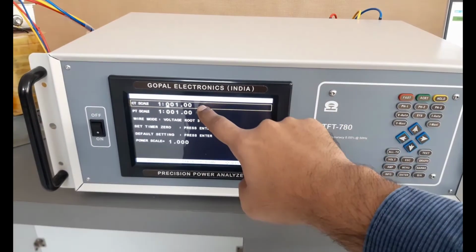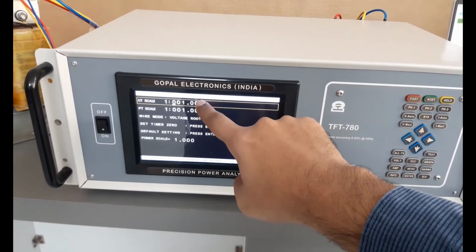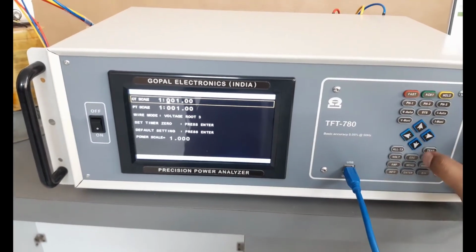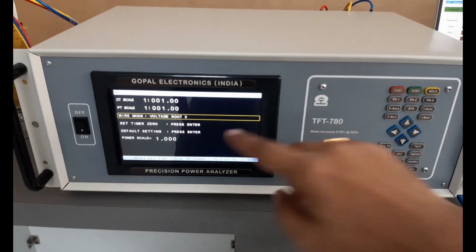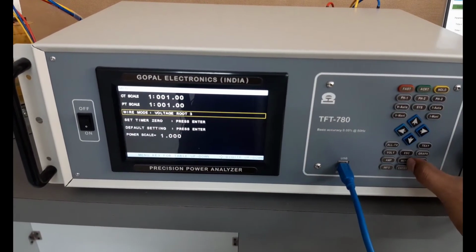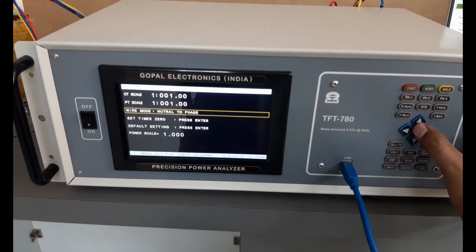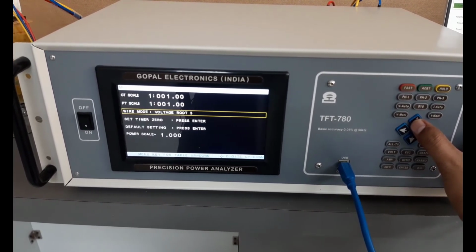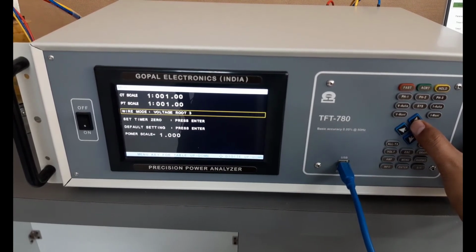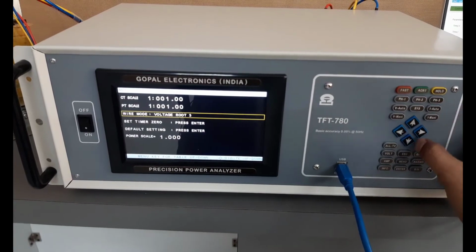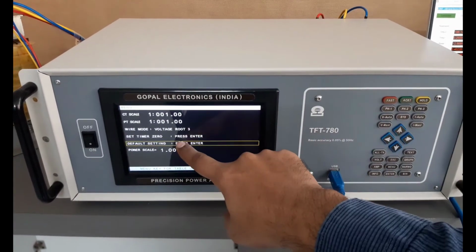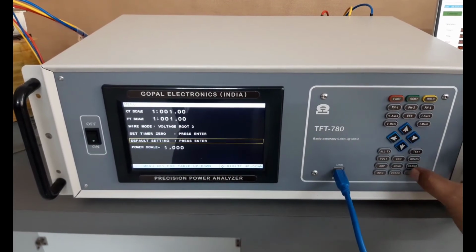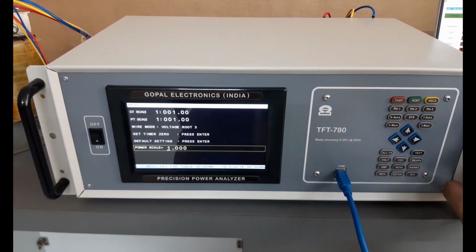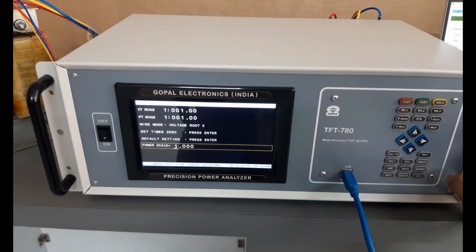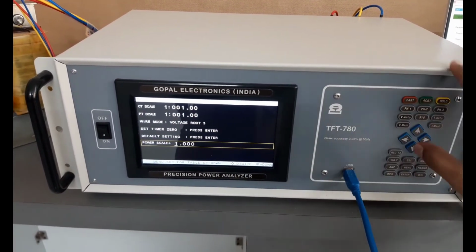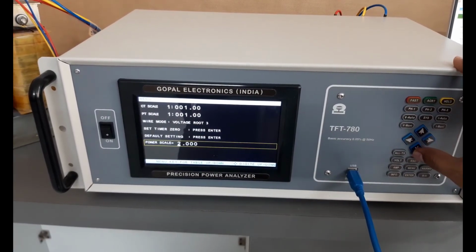This is CT scale. If you are using CT and PT, then you can enter your CT scale and PT scale. This is wire mode. Neutral to phase measurement, 2 wattmeter method, and voltage into √3 mode, means phase to phase measurement. This is default setting. If you press enter, all settings will be default. This is power scale. If you increase the multiplier, it will be a multiplier to power.